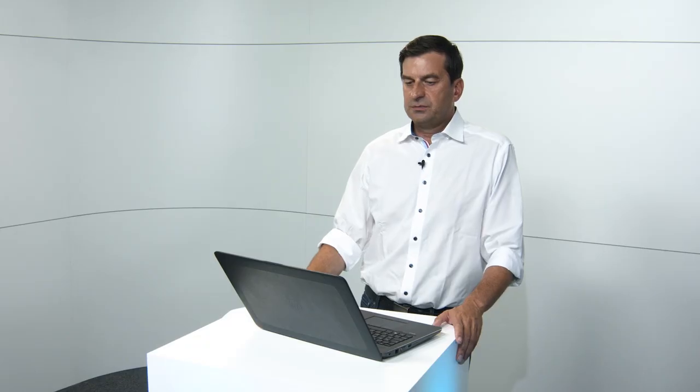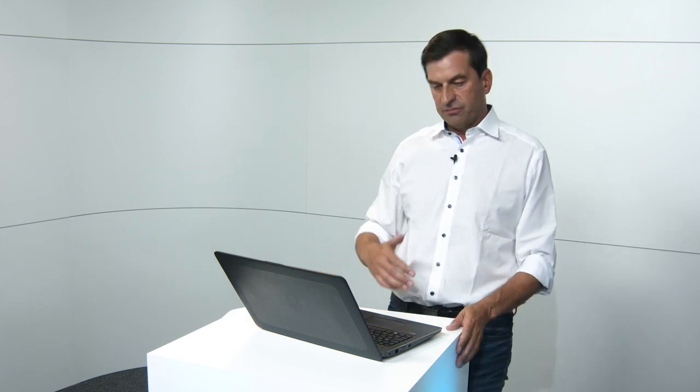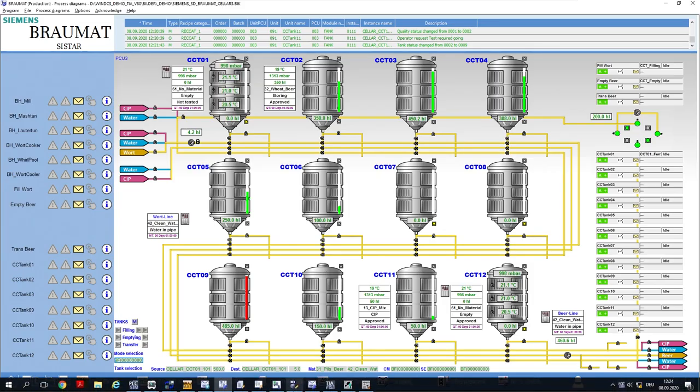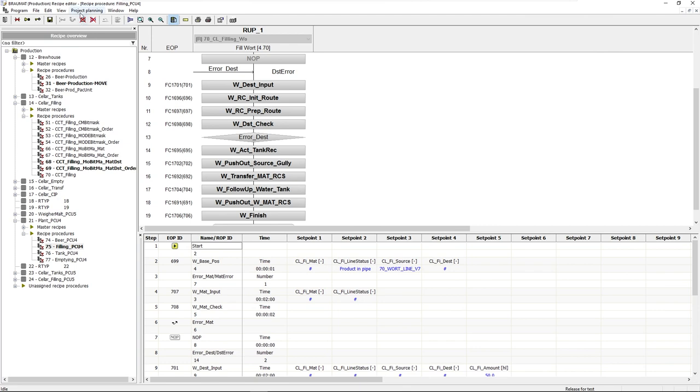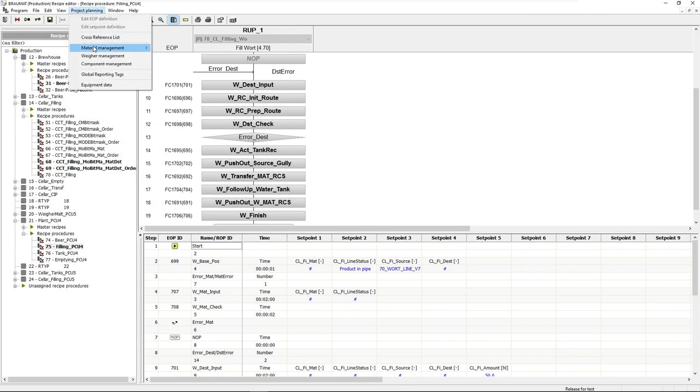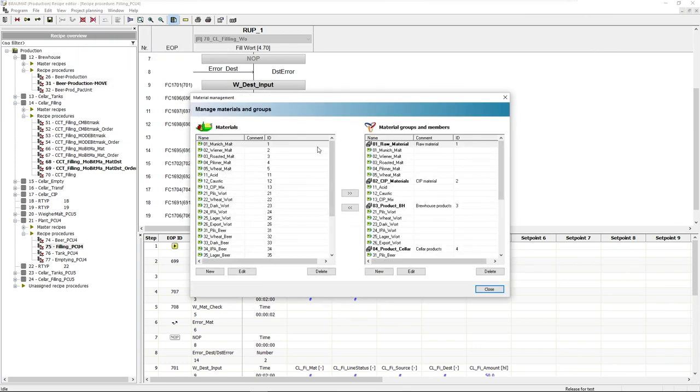Then in order to sensibly transfer materials to or from tanks into other tanks or out of the tank completely, we need a material check. After all, we want to prevent undesired material mixes. You can imagine that certain areas might be undergoing cleaning, so there might currently be cleaning material in a given pipeline. I don't want my transfer order to cause a primary product, in other words, wort or beer, to be transferred through a line that hasn't been rinsed first. So this is why we need material management, which is established within the recipe system.